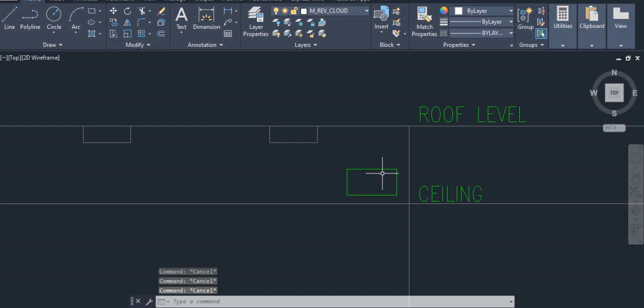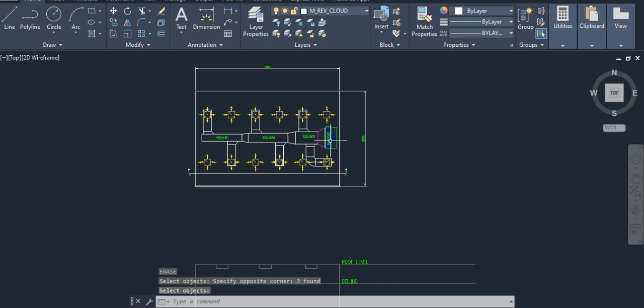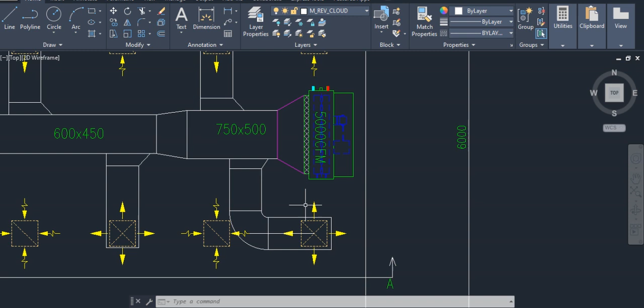When we are selecting the equipment, we get the drawing in AutoCAD from the vendor. But for the first revision drawing, after the heat load calculation, we submit the HVAC selection data for the air handling unit and the fan coil unit, and we send the inquiry to the vendor. The vendor takes a little bit of time to come back to us, but internally the people are pushing us to issue the drawing. So what you should do is always keep temporary equipment blocks: how a fan coil unit looks in side view, how an air handling unit looks in side view. Always keep blocks, side view and top view.